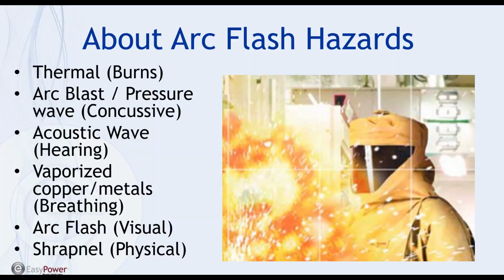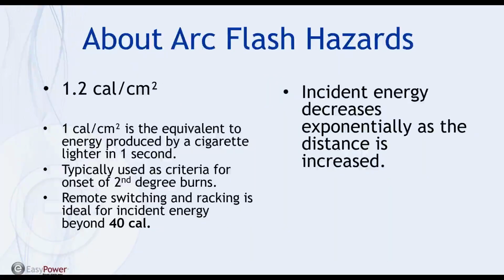And these are all things that, even though we wear PPE, PPE may not always protect against, depending on the incident energy that's there. And this is why we make the case to try to create distance between the arc flash hazard and the worker. So with arc flash hazards, we really start protecting ourselves at 1.2 calories per centimeter squared, and that's the equivalent of a cigarette lighter being lit for 1 second, basically.